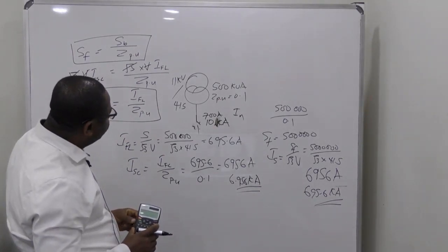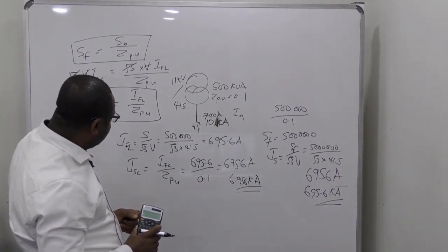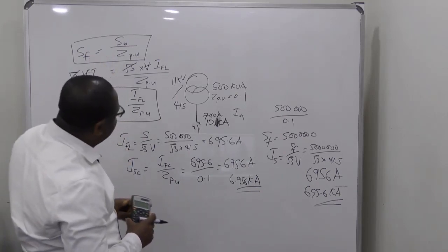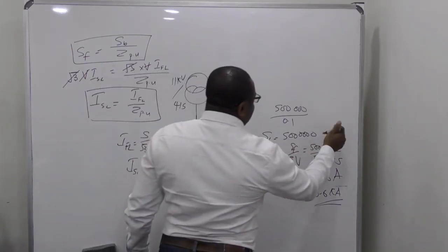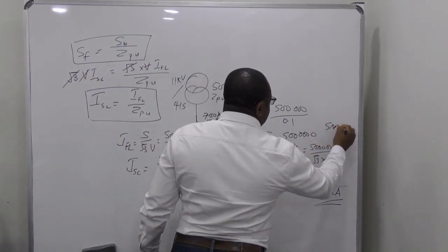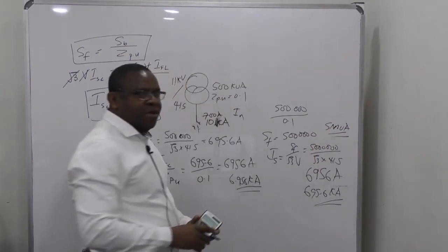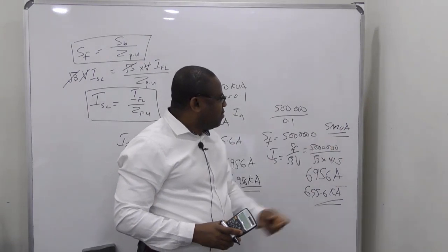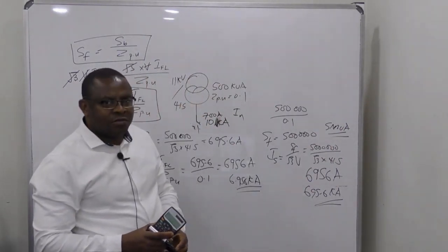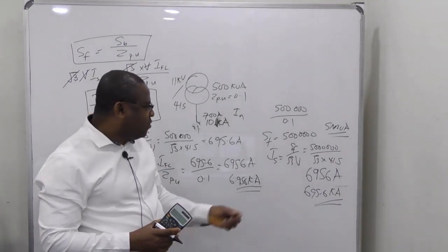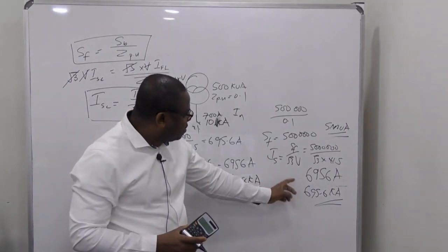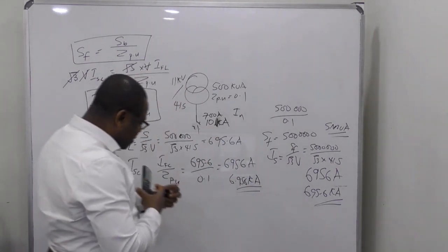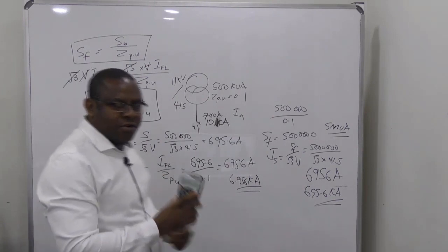Now, what else can we see here? I think that's all. So just know this fault level. Can you see that when I get my fault level, it is about 5 MVA. So either you tell maybe ESCOM or ABB that you need more than 5 MVA switchgear, or that you need a switchgear that is rated 10 kA. All right. Okay, so let's continue the video.